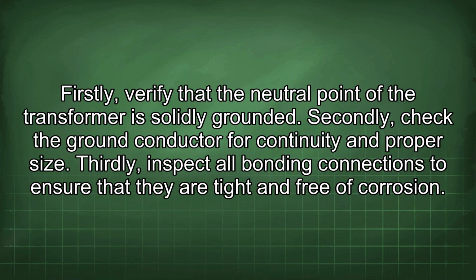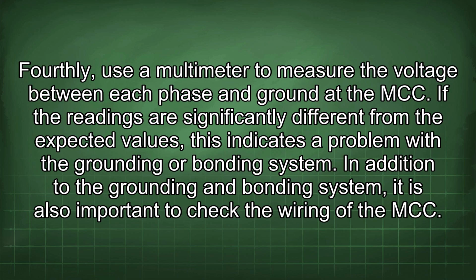Firstly, verify that the neutral point of the transformer is solidly grounded. Secondly, check the ground conductor for continuity and proper size. Thirdly, inspect all bonding connections to ensure that they are tight and free of corrosion. Fourthly, use a multimeter to measure the voltage between each phase and ground at the MCC. If the readings are significantly different from the expected values, this indicates a problem with the grounding or bonding system.